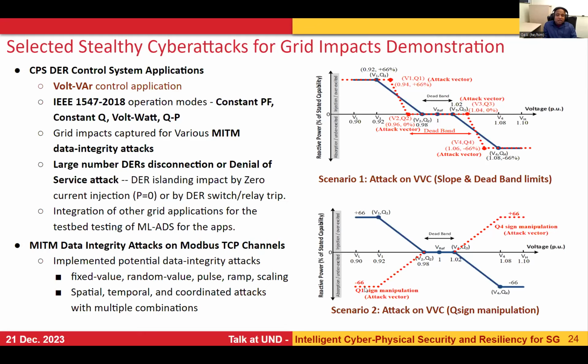In this case, when the system experiences low voltage, like less than 0.98 for example, ideally it must inject reactive power so that it can boost the voltage profile. But because of this new attack vector, the inverters that see low voltage further consume reactive power, and vice versa, when there is high voltage, they inject reactive power. So that actually leads to instability in the distribution grid.